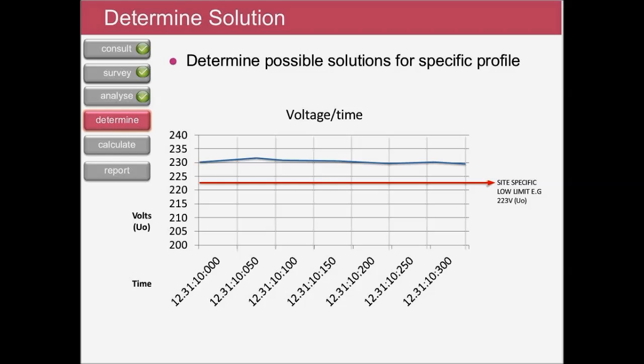So let's add in our optimum site-specific low limit, and we can also plot the critical low limit identified by a specific load. For the purpose of this explanation, we've set this to 206 volts to earth, and using real figures collated from one of our own site studies, we also know that if the voltage dipped below this level for more than 40 milliseconds, a certain item of voltage-sensitive equipment would actually fail and production would be impacted.